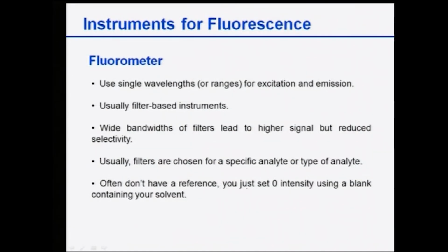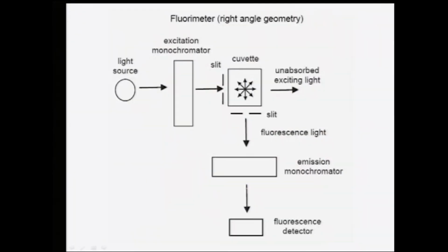And there are different properties of the fluorometer. A fluorometer has single wavelengths, it has filter based instruments, it must have wide bandwidth, and filters are chosen for specific analytes, and we do not use any reference also.